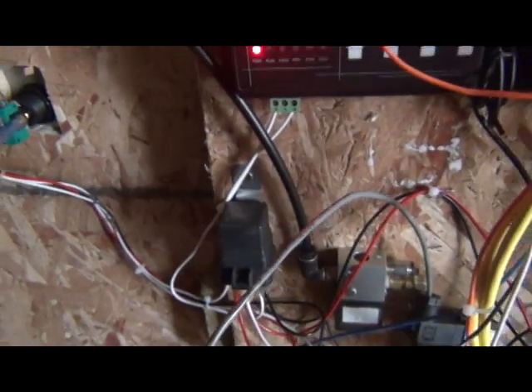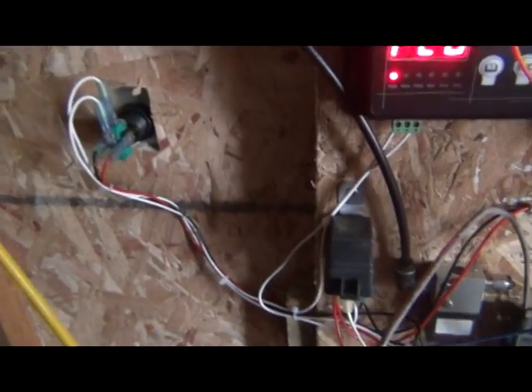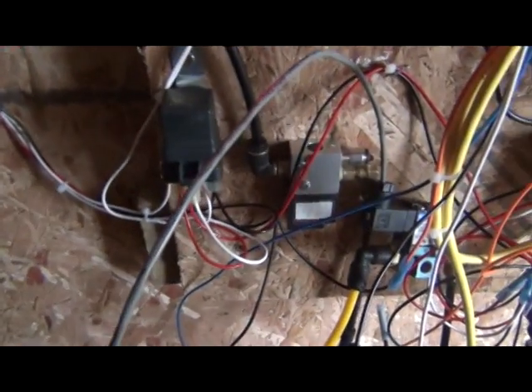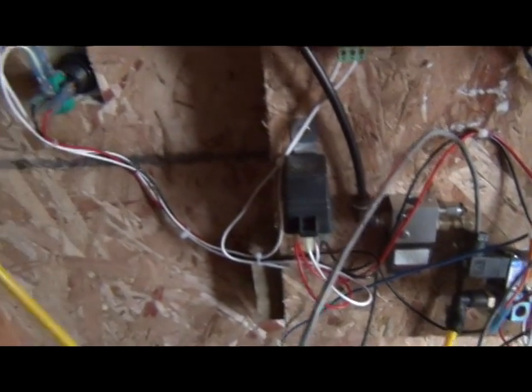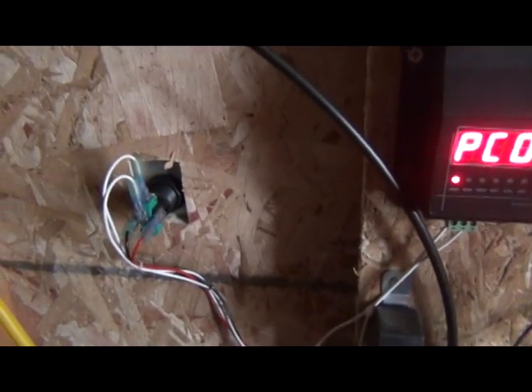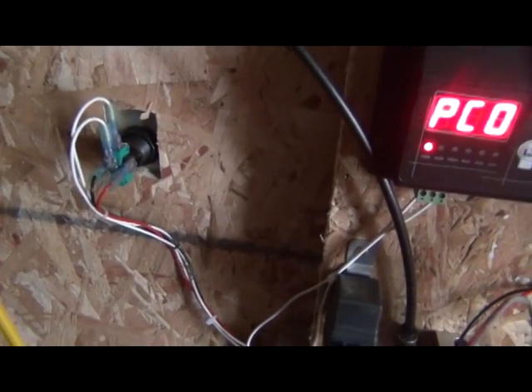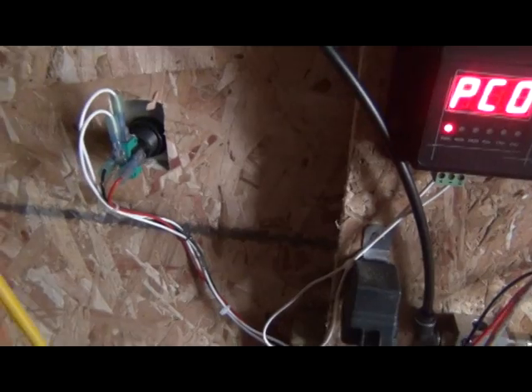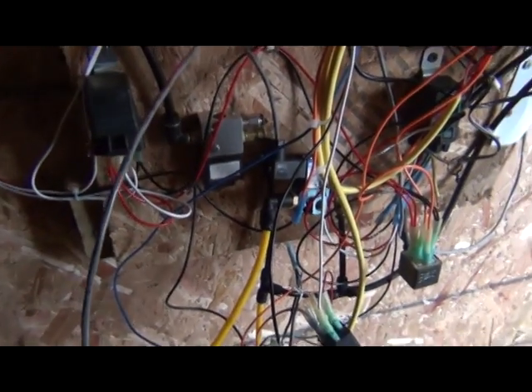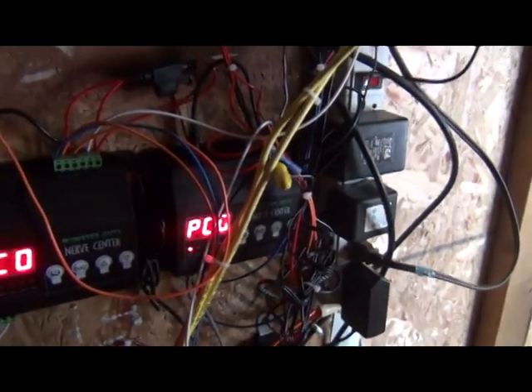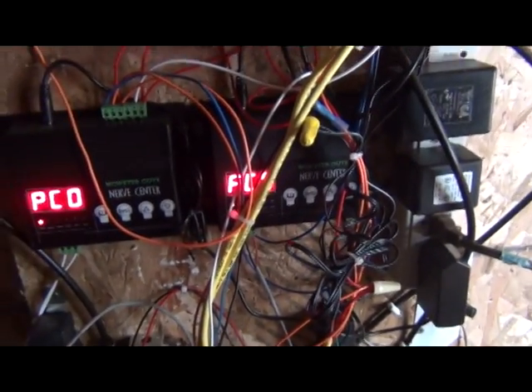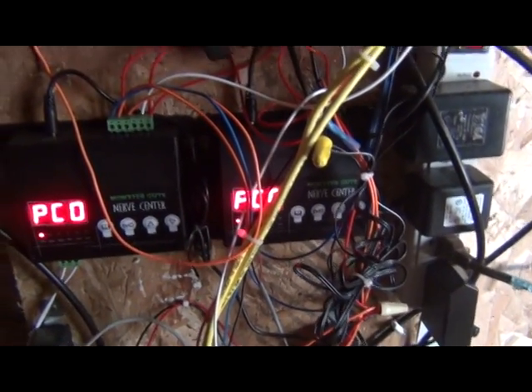It opens or calls the elevator, sends the elevator down. And that will not get power until the other door is totally closed and that's why that relay is there. Otherwise, if they're in the elevator, they can push the button before the door's closed which takes away from the effect. So those are the controls for the elevator and it shows the operation.